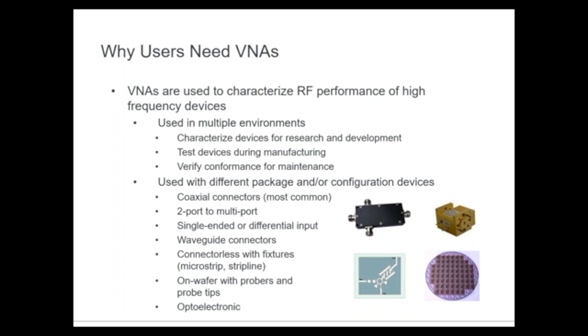VNAs are used in multiple environments. We characterize devices in R&D and engineering, test devices and subsystems in manufacturing, and we also have needs for VNAs in the field to test at cell sites and other remote installations. VNAs are used with different packages and configurations, and this is where the challenges lie when trying to perform user calibration — how do we interface with the VNA, do we need fixturing, do we need a probe station?